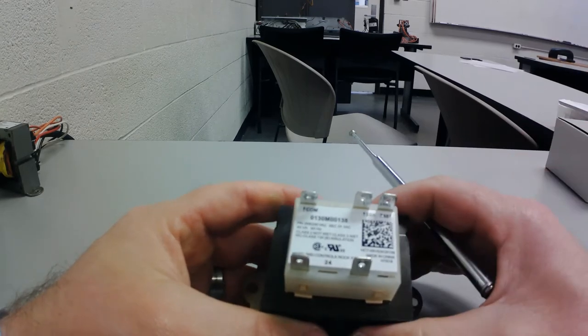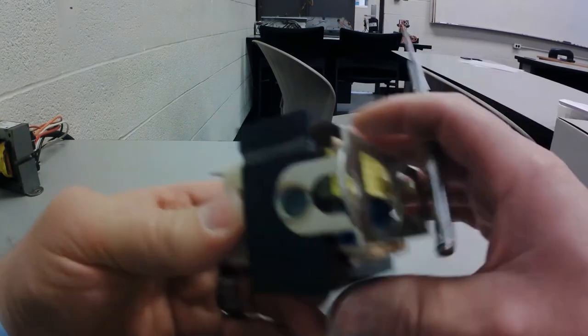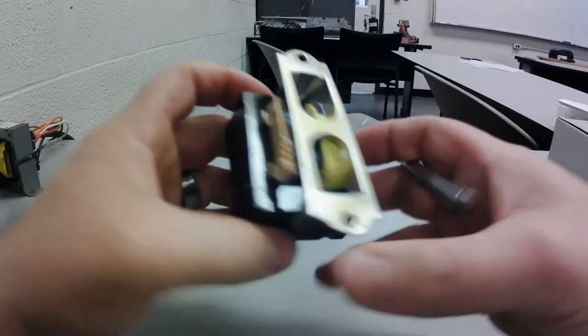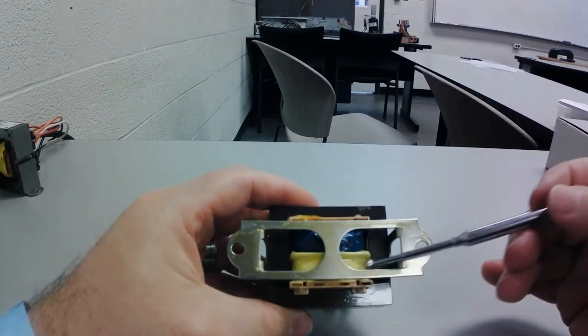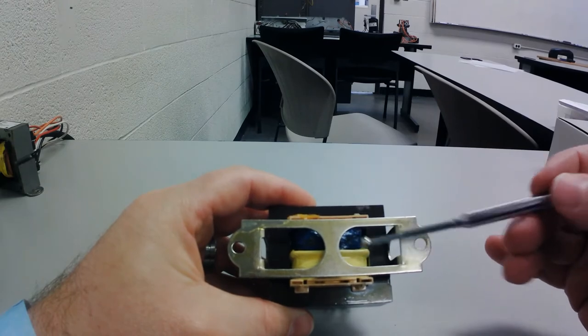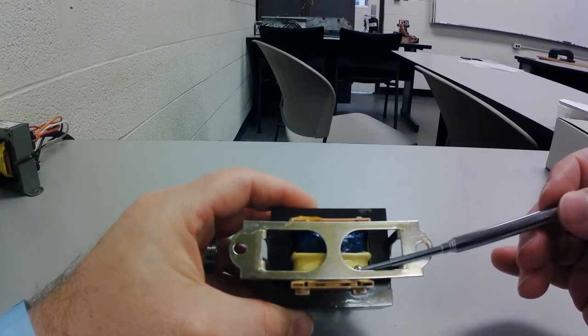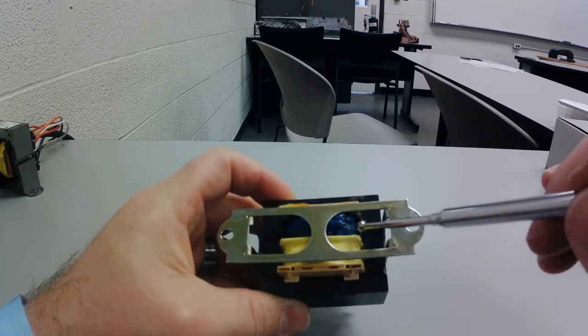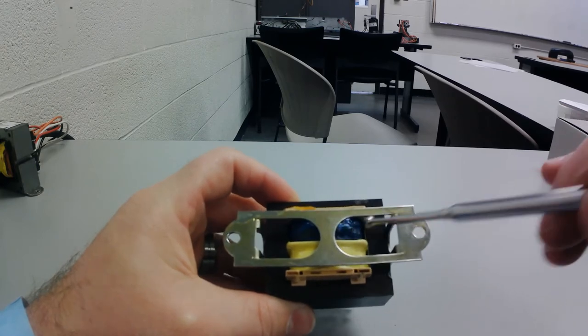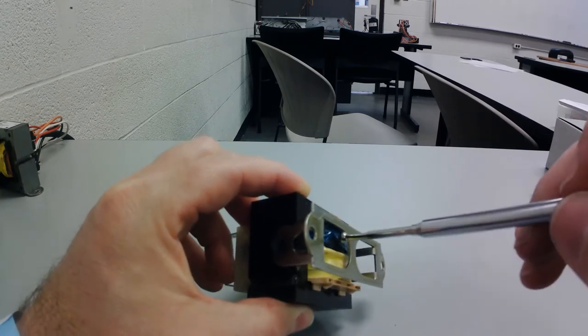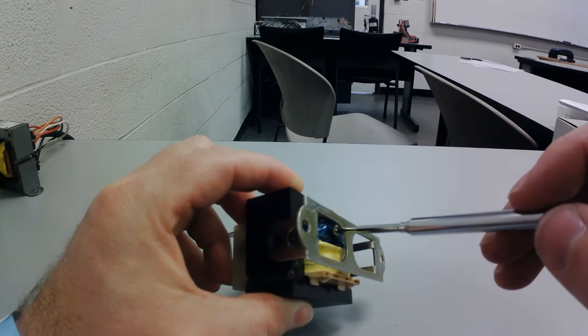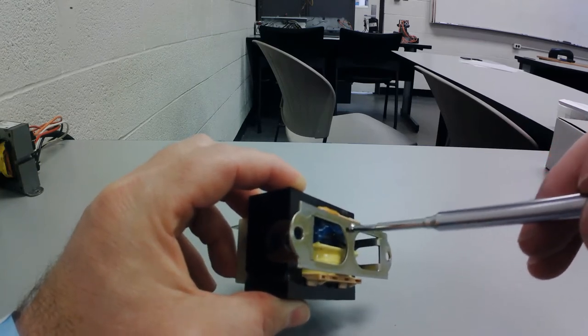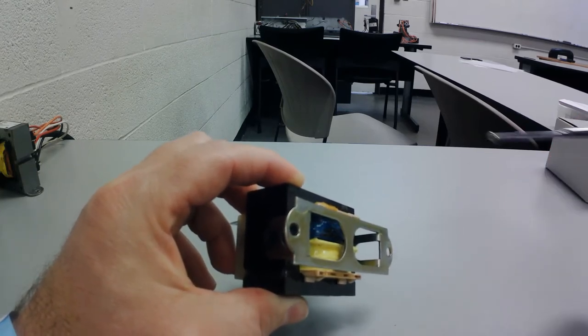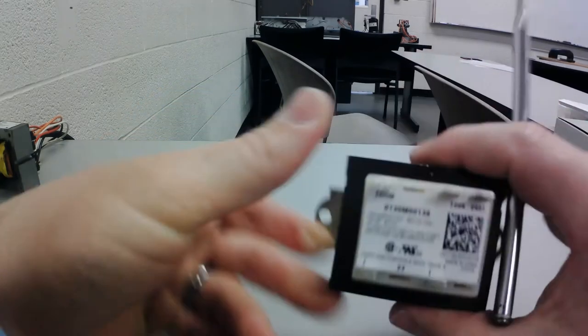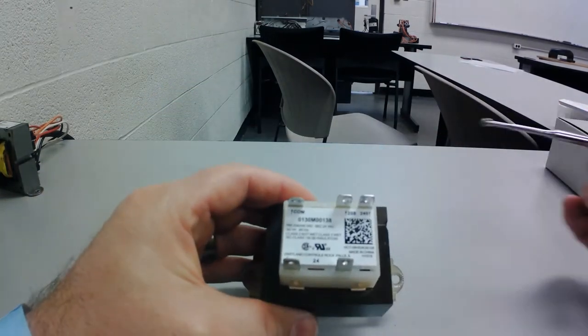I'm going to show you one. Now this one was damaged, and you can see these are my two windings on the transformer. This is my high voltage and this is my low voltage. And you can see that the insulation is charred and kind of burnt up. I hope you can see that. But basically the voltage was applied wrong on this one and this transformer was cooked and it is no longer good. So we had to do a replacement. So we're going to replace it.